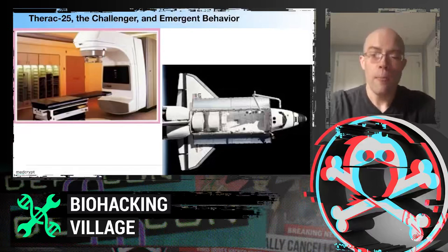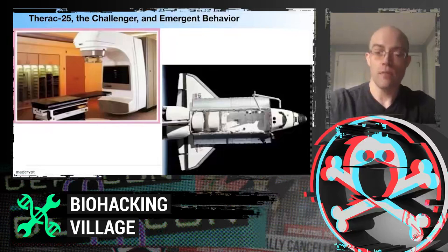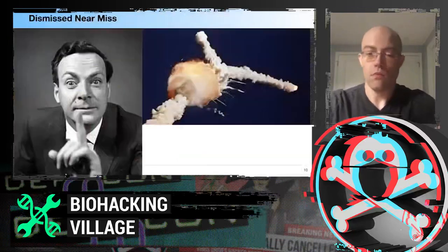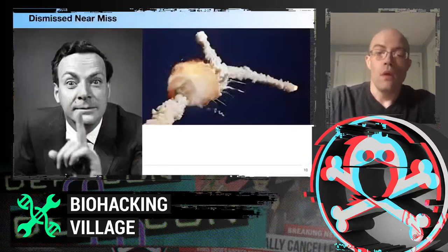Don't get me wrong, device manufacturers absolutely need to test to reduce risk. However, you will not know the extent until it's marketed. That's a fact. That's why the bar for marketing is not 100% safety and 100% effectiveness. The legal bar is reasonable assurance of safety and effectiveness. And in complex systems with emergent behavior, we need to collect post-market data, which they do. It's just suboptimal.